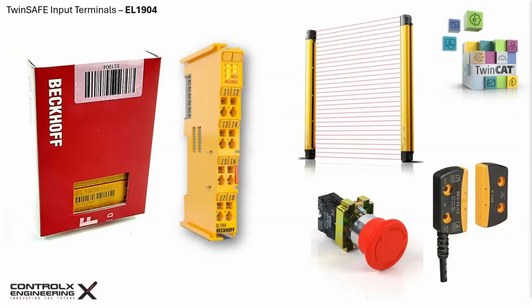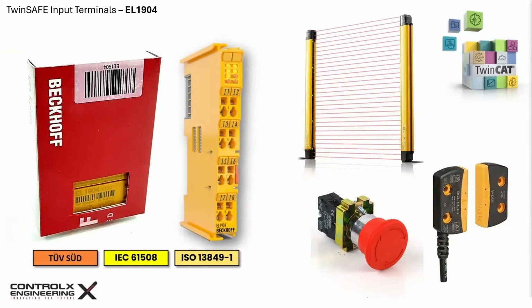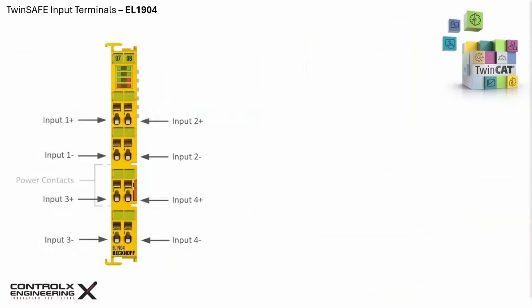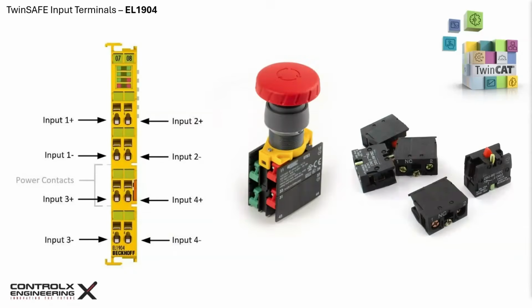Like the logic terminal, it is also certified by TUV to meet SIL 3 according to IEC 61508 and Performance Level E, or PLe, according to ISO 13849-1. The EL1904 has 4 fail-safe input channels and accepts potential free contacts. What this means is that instead of accepting external 24-volt signals like a regular digital input terminal, the EL1904 monitors contacts like those of an e-stop. I will explain the exact mechanism in a little bit. The EL1904 also has 4 green LEDs to indicate the status of each of the 4 input channels.